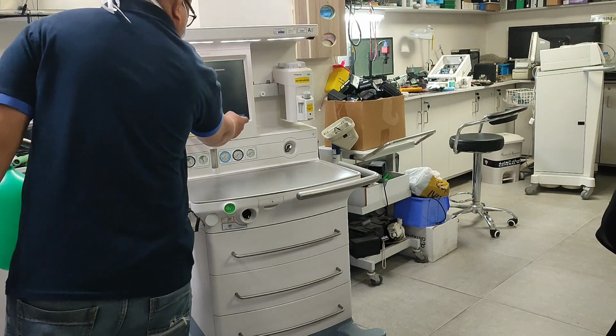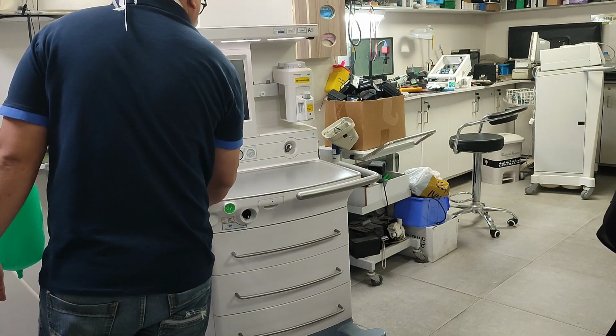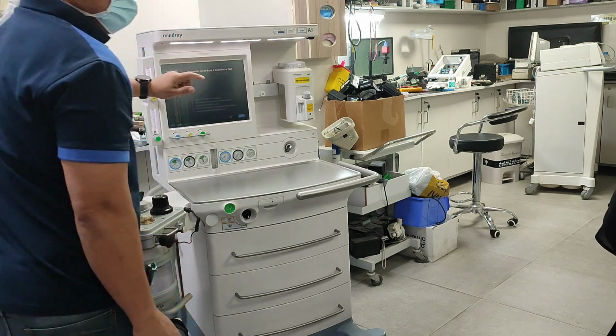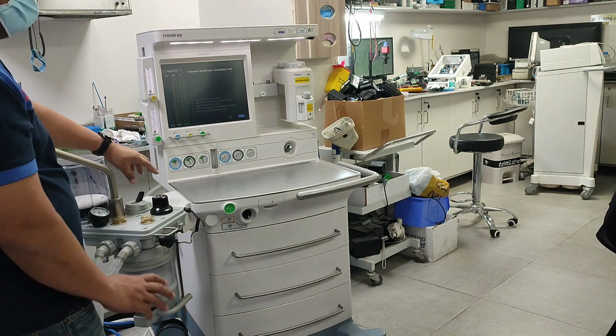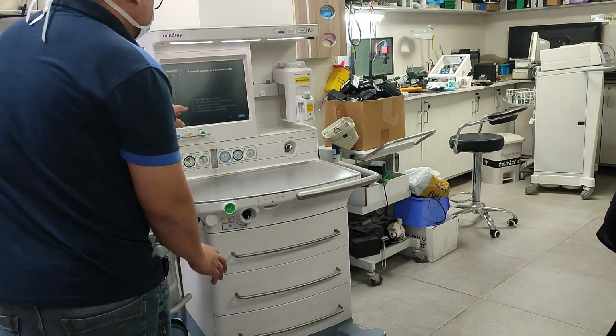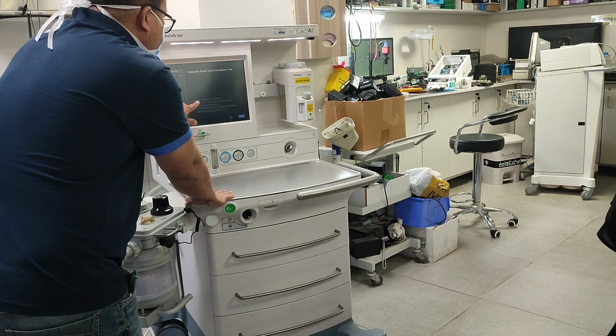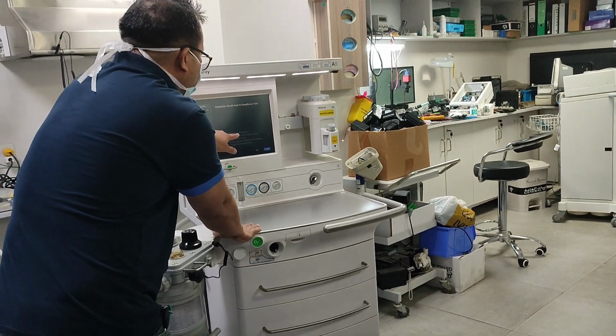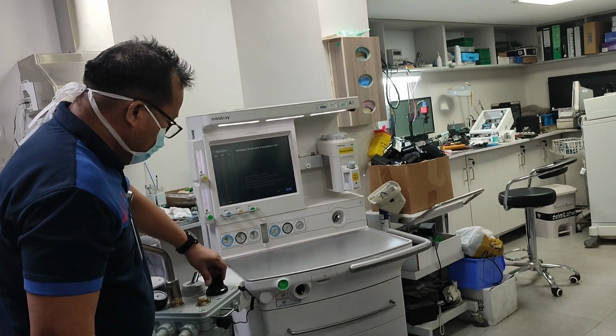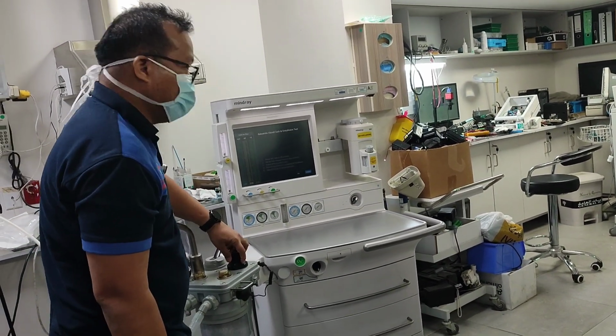So still the gauge is not coming down. Go to continue. And now we do the automatic circuit leak compliance test. Before, we were doing the manual. Now we are doing the automatic. In the automatic, it will tell you everything you need to do on the screen. Adjust APL valve to SP position. We are at 75, so we will go to the SP position. So this is the SP position.